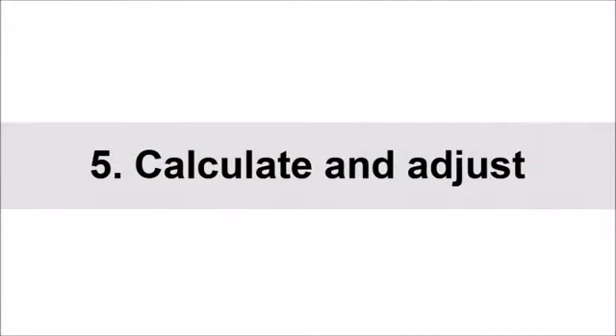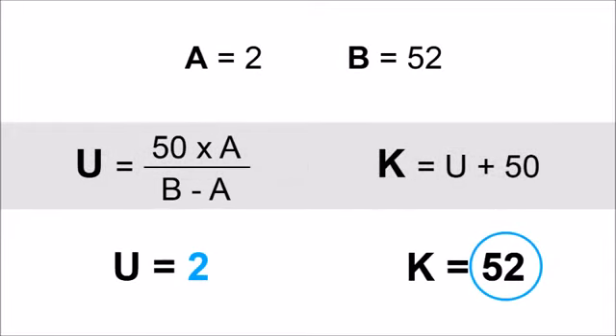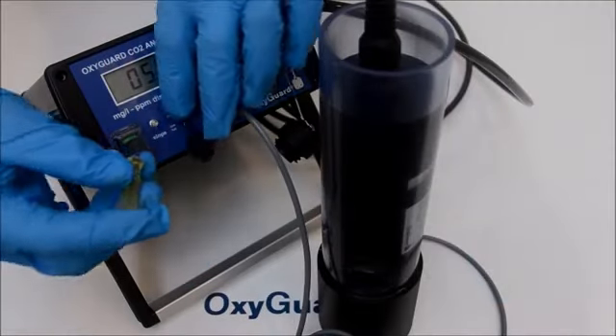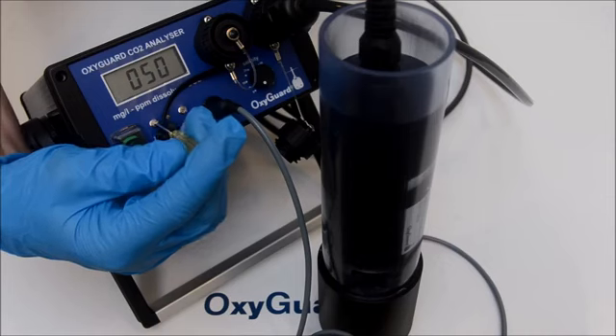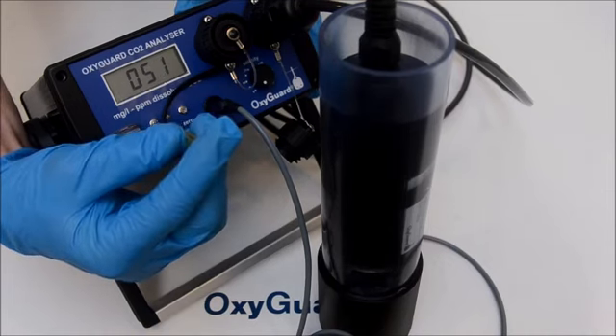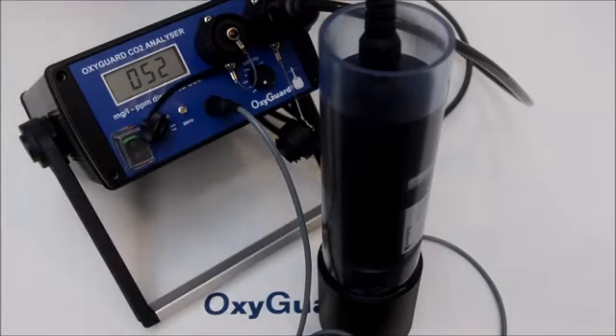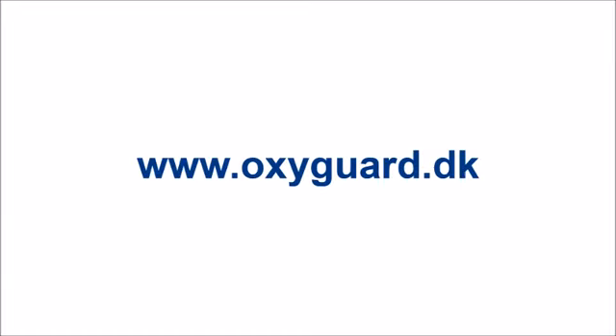I can now calculate the calibration value and adjust the analyzer. First I need to calculate the U value. To do so, I'm going to multiply the A value with 50 and divide by the difference between B and A. The result is 2. Second step is to calculate the calibration value, K. To do so, I'll add 50 to the U value, which I got in the previous calculation. Write the number down. I can now adjust the slope screw until the display shows the value. Stop the stirrer, remove the probe, discard the water in the beaker, rinse and dry the parts. Calibration is now completed.